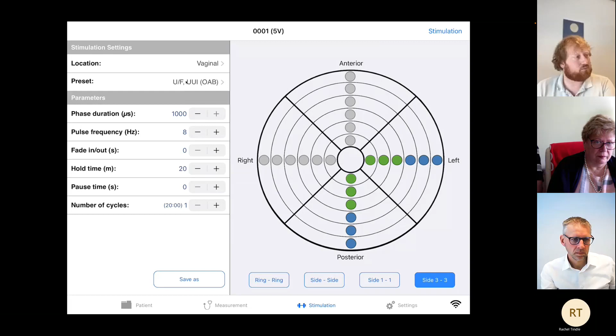We have extensive guidelines that show you how to use them and what you should do if a patient has one of these conditions. But I always say that this is a very good starting point for that specific patient. So it's 95% there, but you can fine tune it for the specific needs of the patient as well by pressing the plus and the minuses at each preset or each parameter. You can also create your own presets, and they are stored below here by pressing the Save As button, and then you can create a name and store the preset with the settings you have selected here.